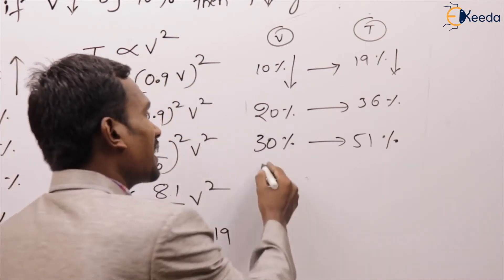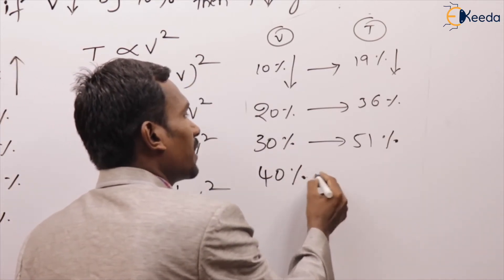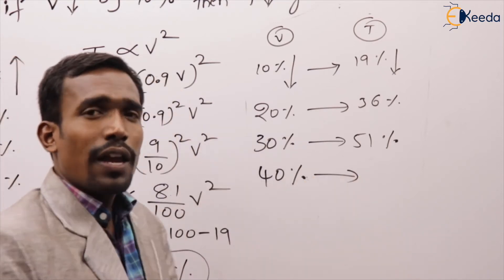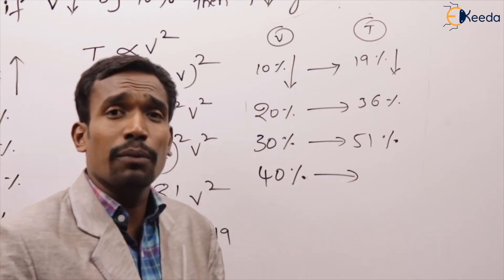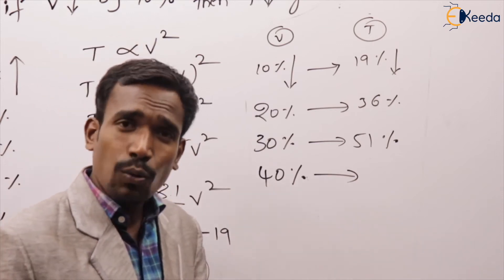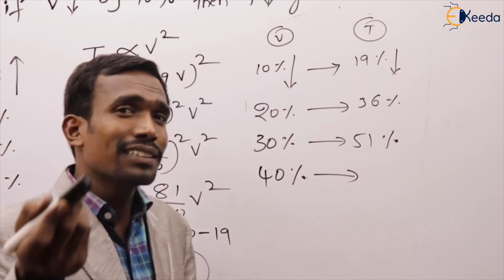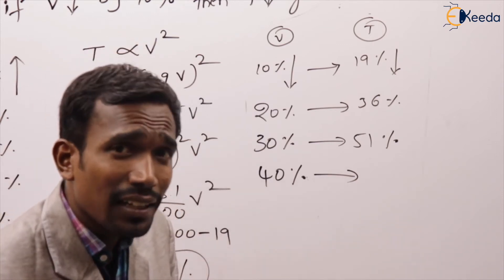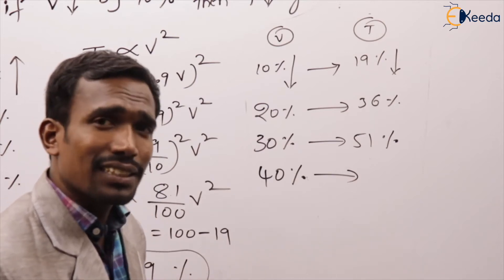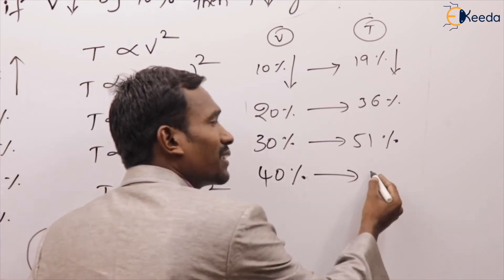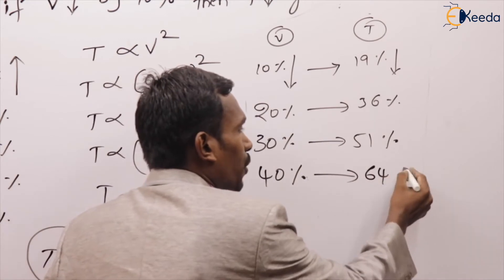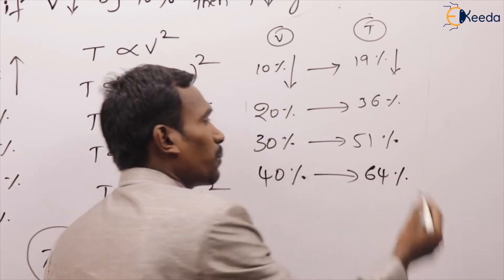If voltage reduced by 40%, the factor is 0.6, so 6 squared = 36, meaning 100 minus 64 — torque reduced by 64%.